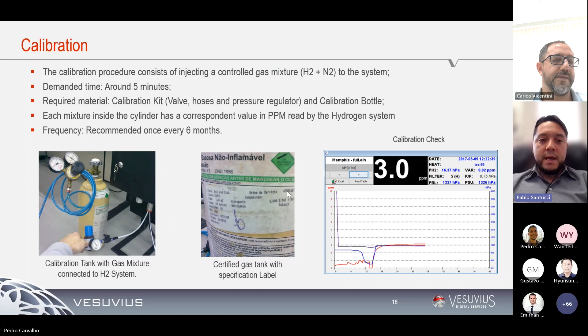Not only calibration gas, but also checking the leak of the entire system is recommended, because any kind of leak can and will influence the final readings of our system. So keeping a perfect sealing in the entire system is the best. So every time a part needs to be changed, for example a lens, a pole or a hose inside our system, it's highly recommended that a leak test be put in place so that once again we can guarantee there's no leak being built after this swap.